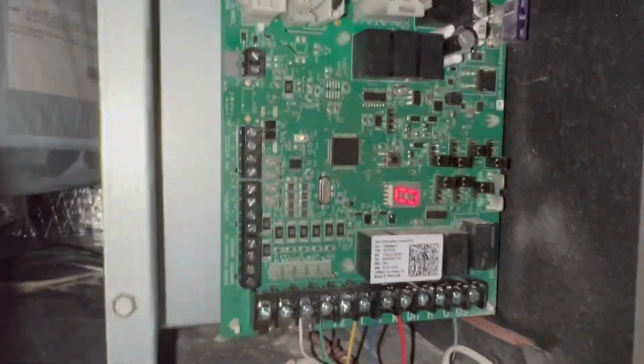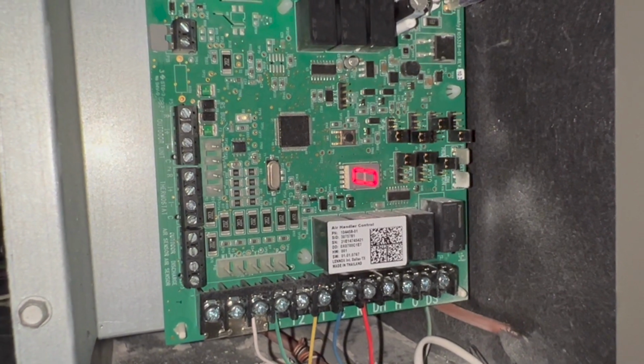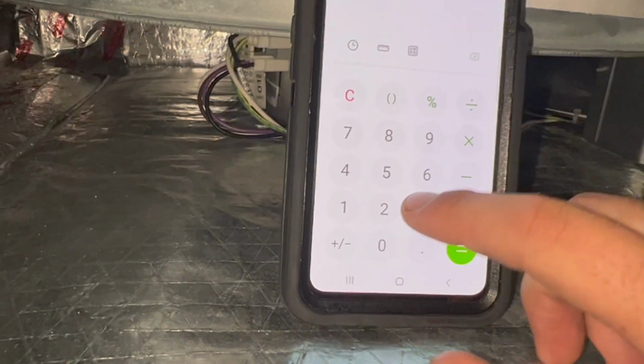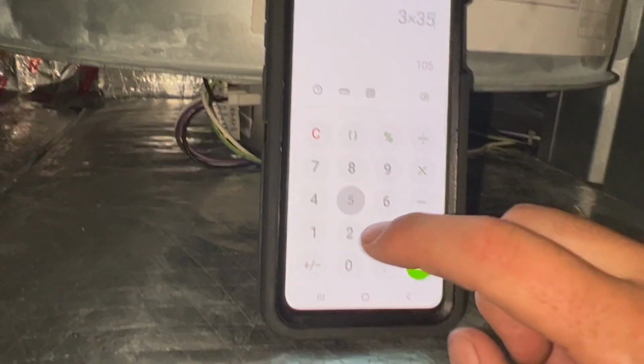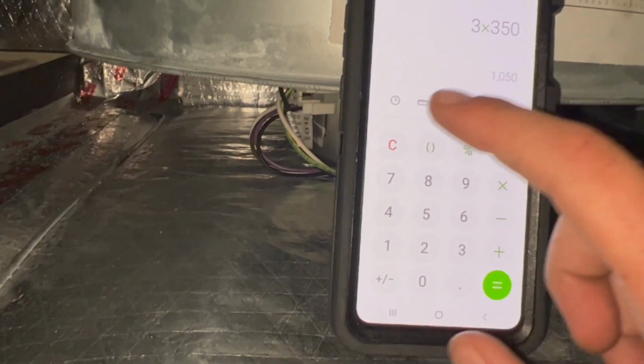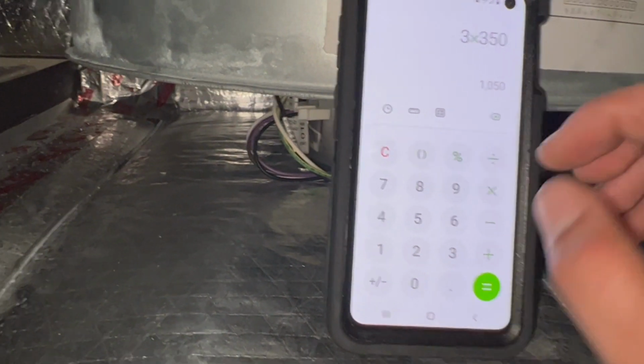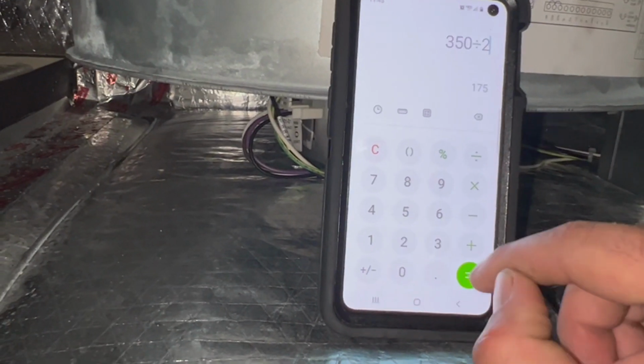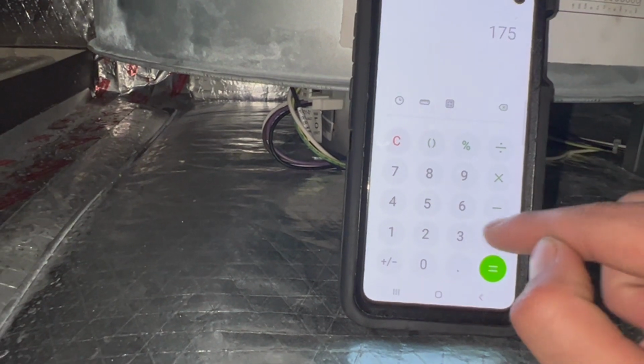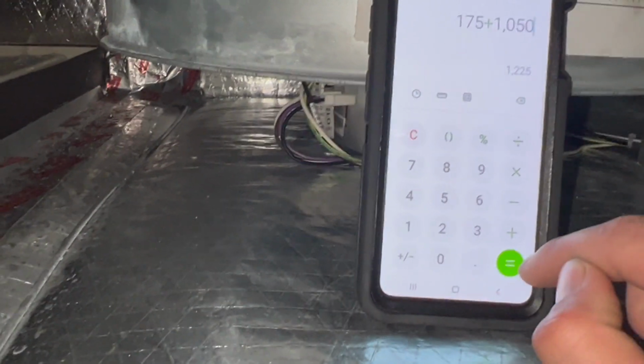So we got 1080 CFMs. So if we go 3 tons times 350 per ton is 1,050, and then we add 175 plus 1,050. We need 1,225. So it is a bit below.